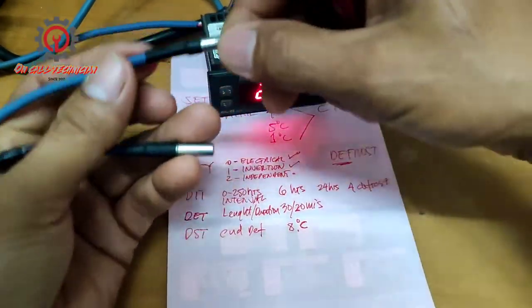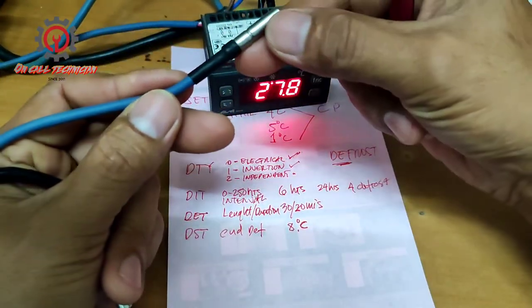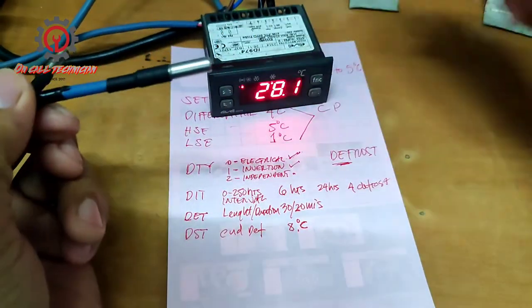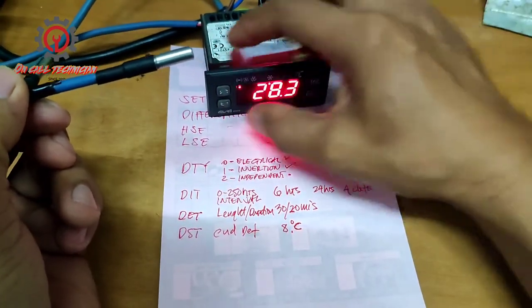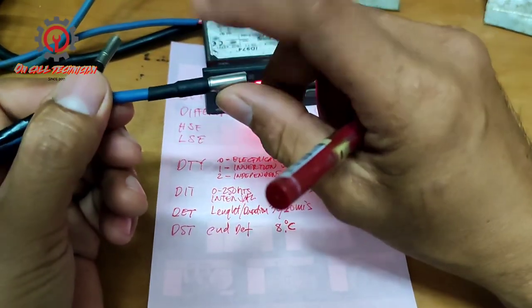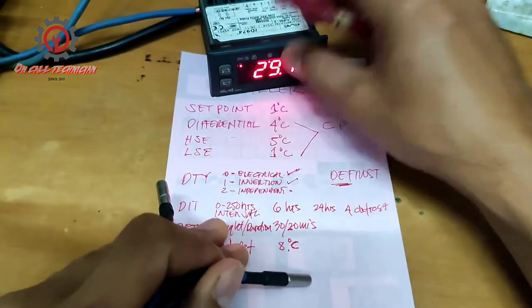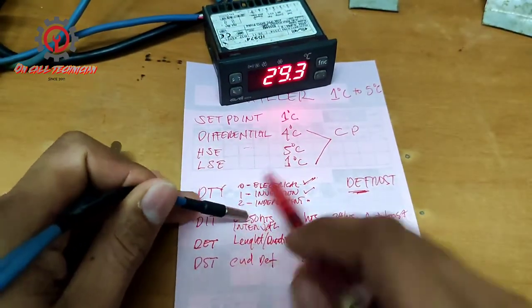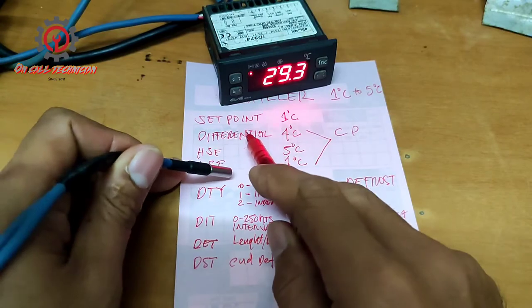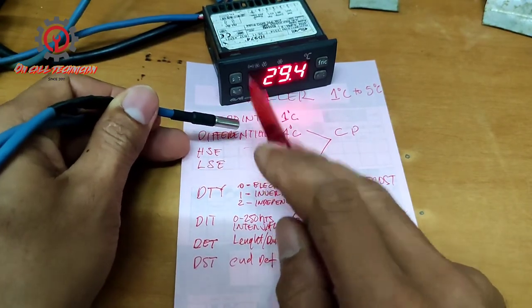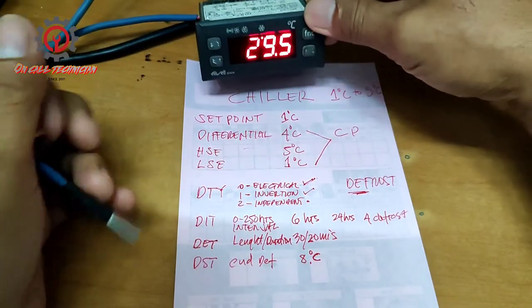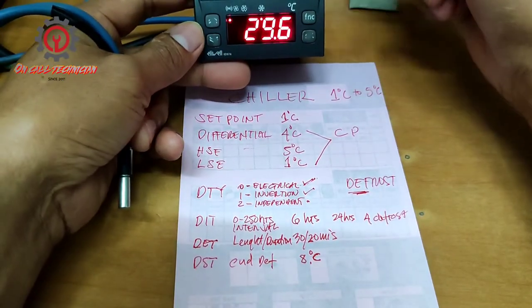The evaporator sensor serves as the defrost end sensor, while the function of the room sensor is to read and control the on and off operation of the compressor. That is the purpose of the differential — that is the role of the room sensor.